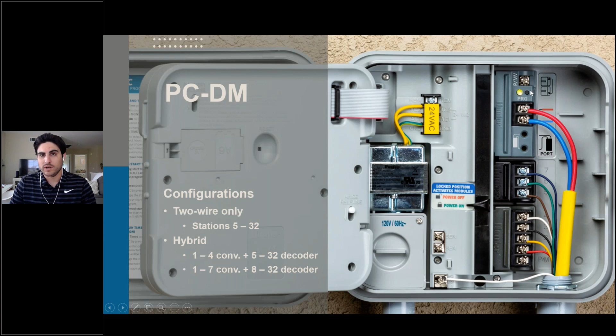A little bit of a learning curve to understand that, hey, if you're just running the PCDM, you're gonna be starting at station 5 and only getting 28 zones in there. Conversely, the EZDM, when used with ICC2 and HCC, is completely flexible. It can be installed in any single one of these output slots. It can run any stations as 2-wire and side by side with any stations as conventional wire there. So it's a little bit more flexible than the Pro C in where you can put the module and how many zones you can get.